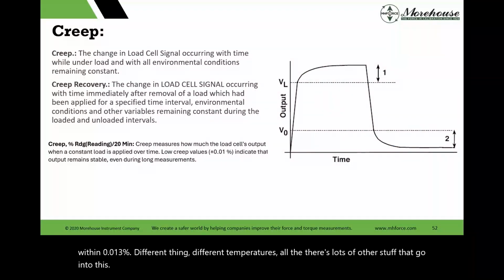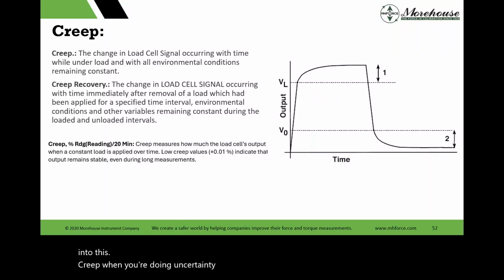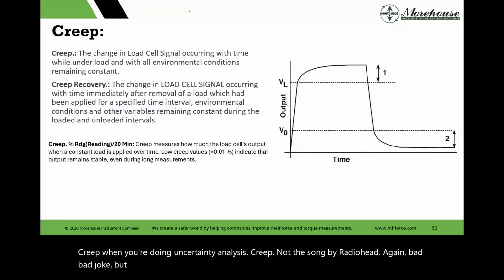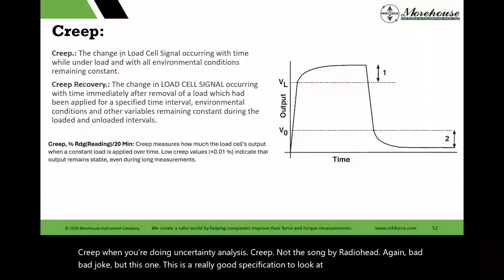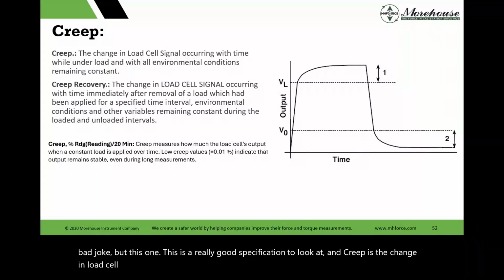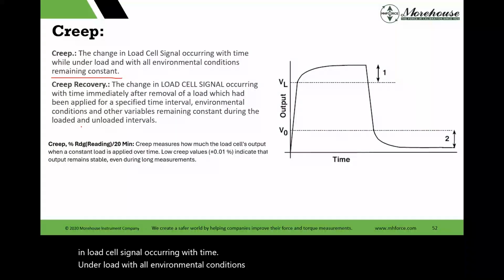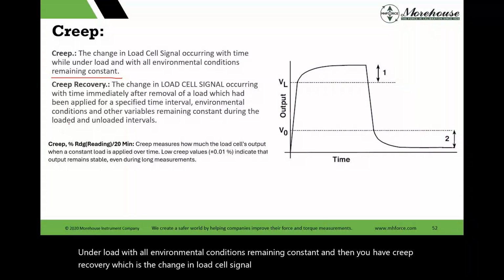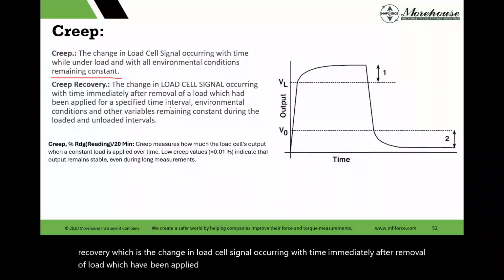Creep, when you're doing an uncertainty analysis. Creep, not the song by Radiohead. Again, bad joke. But this is a really good specification to look at. Creep is the change in load cell signal occurring with time under load, with all environmental conditions remaining constant. And then you have creep recovery, which is the change in load cell signal occurring with time immediately after removal of load which has been applied for a specified time interval, environmental conditions and other variables remaining constant.